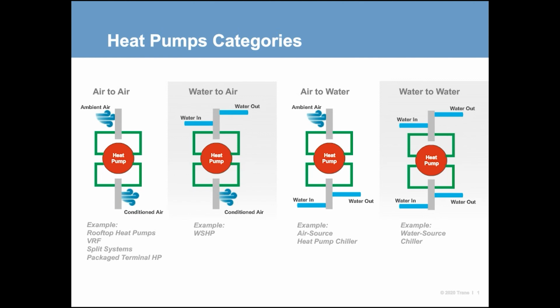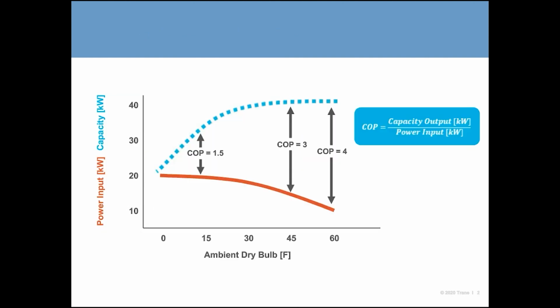What I want to talk about next is some challenges that we see customers facing using heat pump technology. The first one is cold climate operation. Chris talked about this as part of their study: as ambients get colder, heat pumps in heating mode become less efficient. You'll typically hear people say heat pumps are 3 to 4 times more efficient than electric resistance, which I totally agree with, but it's also dependent on that ambient.